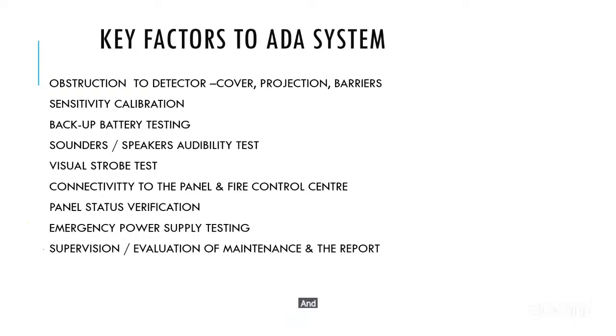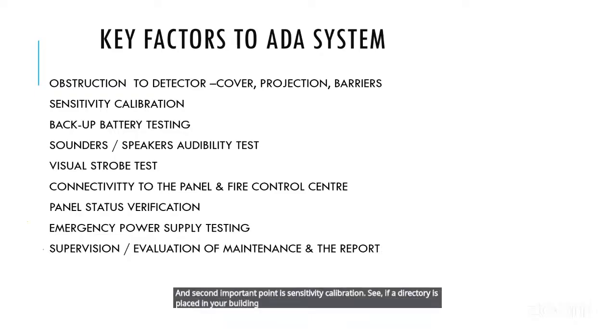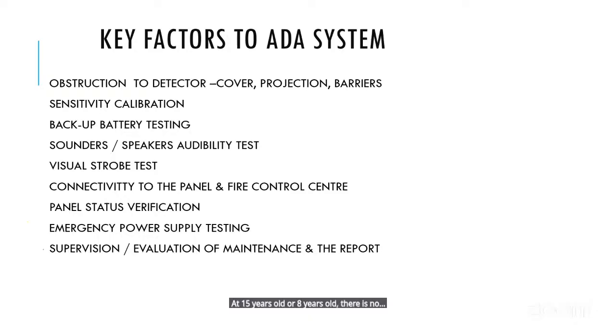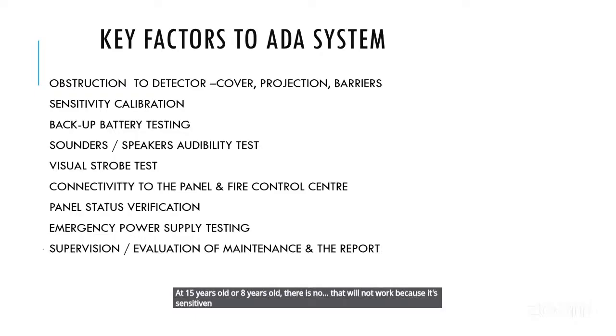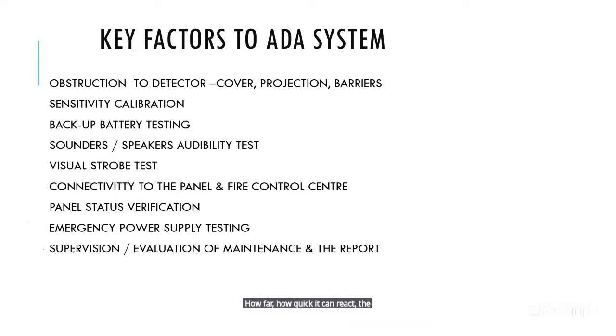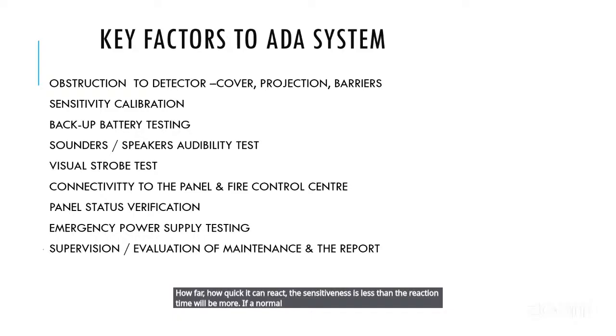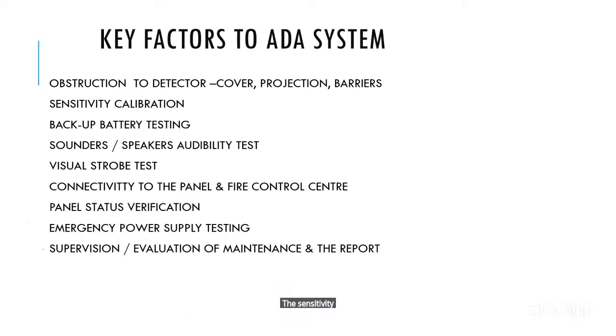And the second important point is sensitivity calibration. If a detector placed in your building is 10 years old, or 15 years old, or 8 years old, it will not work properly, because of its sensitiveness: how sensitive it is to feel the smoke, how far, how quick it can react. If the sensitiveness is less, then the reaction time will be more. A normal, fresh detector reacts within 30 or 40 seconds, but if the sensitiveness is lost, it will take 1.5 minutes.